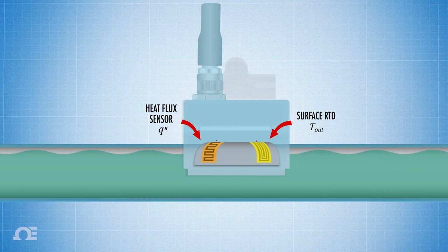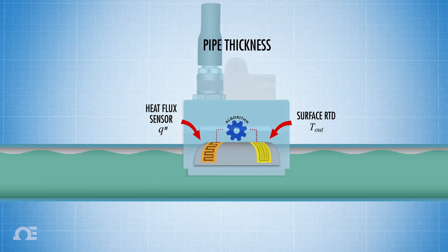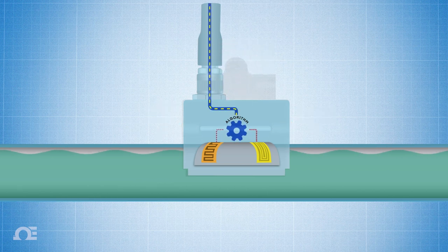And we take those two values and pull them into our proprietary algorithm that's based on Fourier's heat conduction equation that we just developed. And we enter a few user input values, like pipe radius, pipe thickness, and pipe material. Then we can calculate for the temperature on the inside of the pipe.